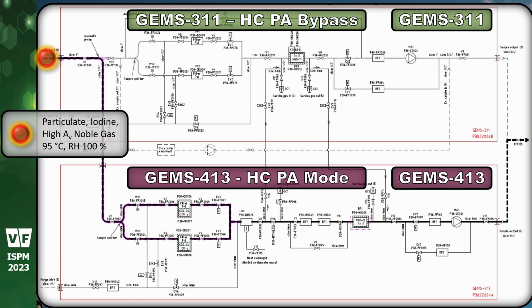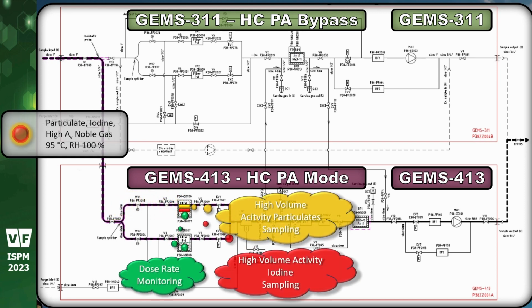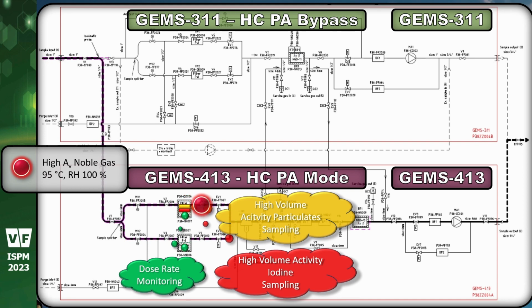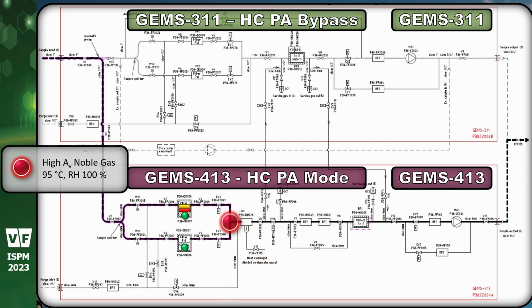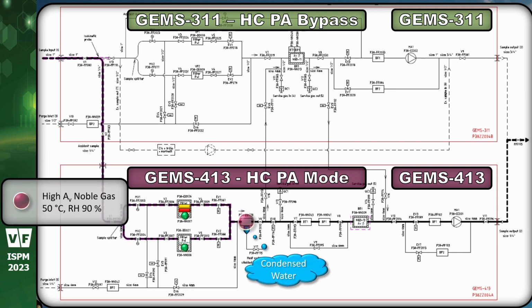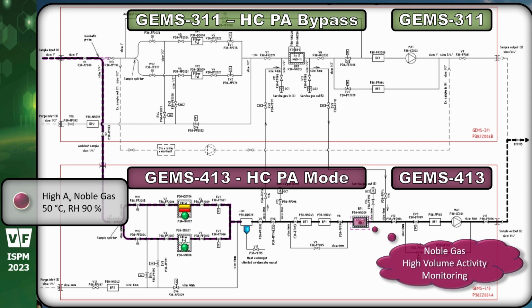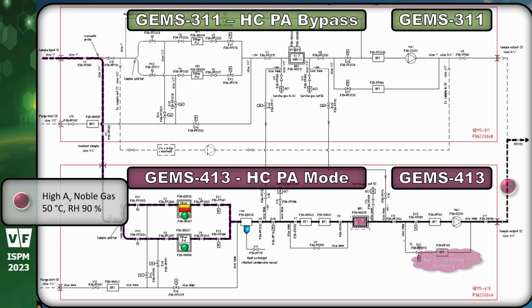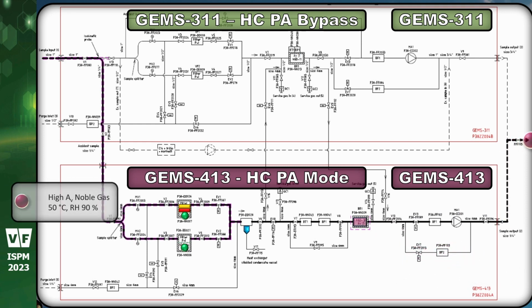The particulates and iodine are separated and collected by particulate filter and silver zeolite cartridge and heated shielded samplers of GEMS-413. Dose rate of exposed filters and cartridges is measured. The maximum temperature and humidity of harsh condition air sample must be decreased to 50 degrees Celsius and 90% of relative humidity in GEMS-413 heat exchanger and condenser. Condensed water is collected. The radioactive noble gases volume activity is measured in the NGD-13 noble gas detector of GEMS-413 and after that air sample is returned to the ventilation stack.